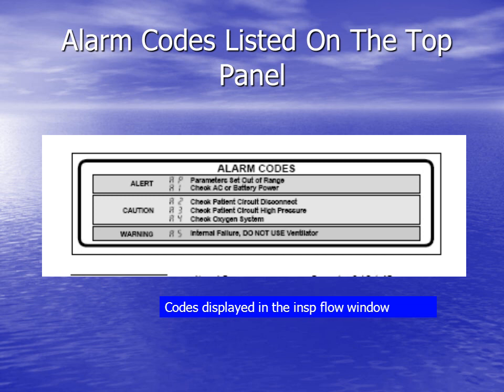It could be triggered for a low pressure or apnea. A3 is triggered for high pressures. A4 relates to the high pressure O2 source. And A5 might alarm because of a frozen piston or a microprocessor failure. If you see an A5 displayed in the inspiratory flow window, do not use the vent.